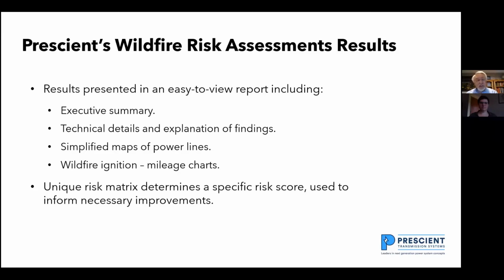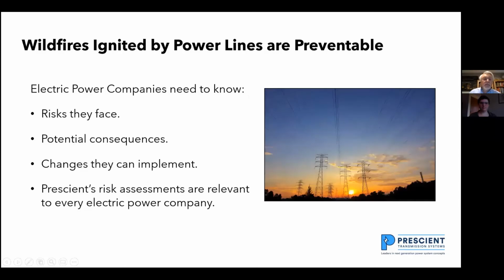like protective relaying changes, and tell you if you change your relays from electromechanical to microprocessor, and if you use your microprocessor-based relays with setting groups that vary with ambient temperature or wind speed or weather history, that would change this risk score. So these are things we can do, and they're things we should be doing. Electric power companies need to know the risks they face, and they need to know the potential consequences. We're here to identify changes they can implement and to show power companies things they could do to become industry best.